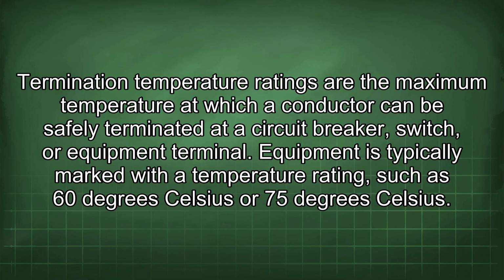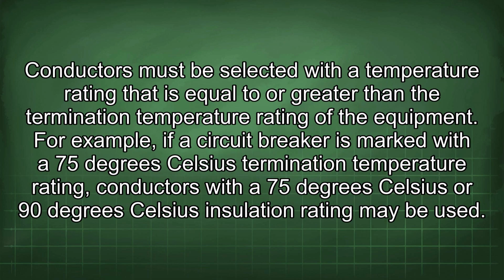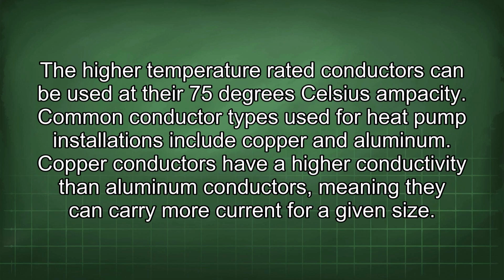Termination temperature ratings are the maximum temperature at which a conductor can be safely terminated at a circuit breaker, switch, or equipment terminal. Equipment is typically marked with a temperature rating, such as 60 degrees Celsius or 75 degrees Celsius. Conductors must be selected with a temperature rating that is equal to or greater than the termination temperature rating of the equipment. For example, if a circuit breaker is marked with a 75 degrees Celsius termination temperature rating, conductors with a 75 degrees Celsius or 90 degrees Celsius insulation rating may be used. The higher temperature rated conductors can be used to their 75 degrees Celsius ampacity.